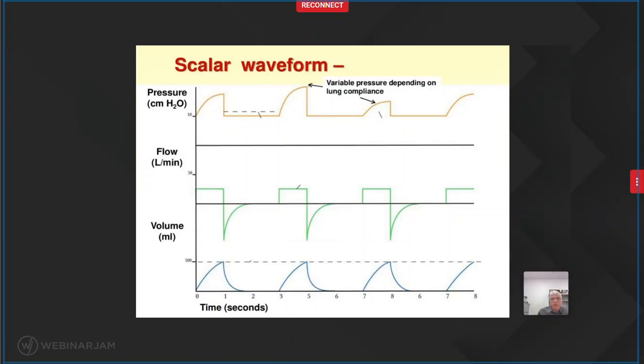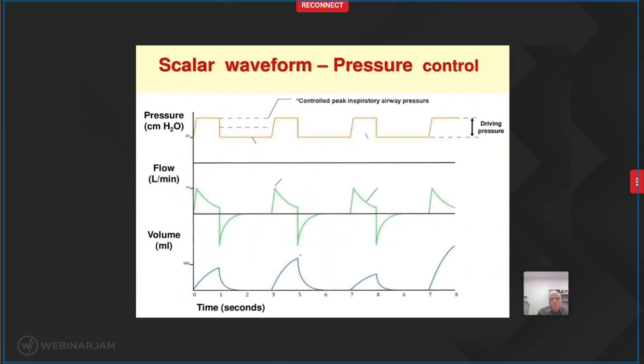Okay. However, when you look at the waveform during pressure control, now, first of all, you can see now that the pressure is constant. Every single breath is the same. This pressure waveform is square, and now the flow is decelerating. And again, now what is changing is the volume. The volume now is irregular. So you have a small volume here, a large volume here, a small one here, because now the volume delivered for that pressure will be secondary to the compliance of that lung. So if the compliance is very low, your pressure will be achieved faster, and so you get less volume. If your compliance is normal or high, then you're gonna get a lot of volume into the lungs with the same pressure.